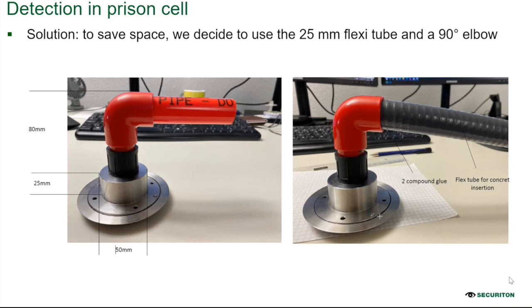And this is a very important aspect because maintenance in the prison is otherwise very difficult. So the next question is, can I use a single ASD to protect several cells? Yes, it is possible within the limits allowed by the fire zone. So limits on maximum zone size, number of rooms, etc. But here you have to see your specific local regulation for that.